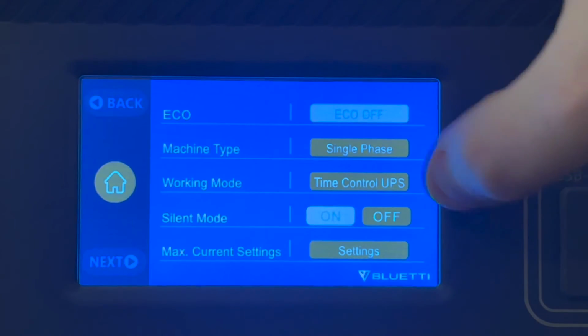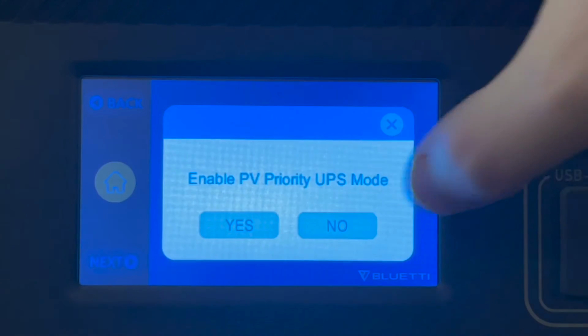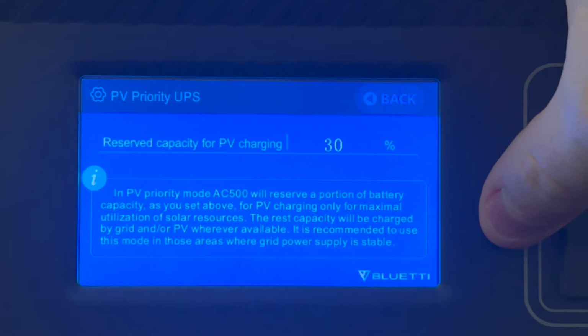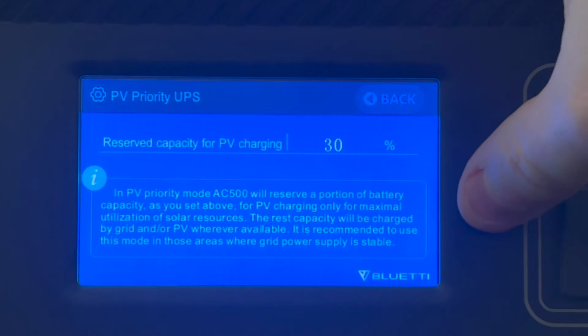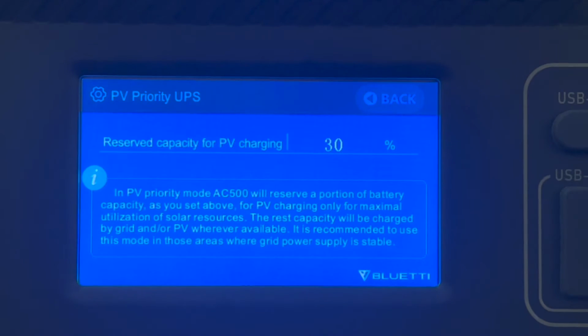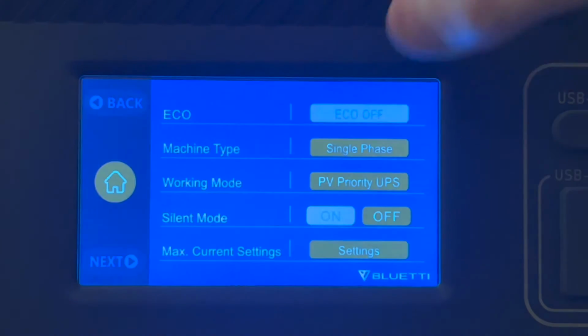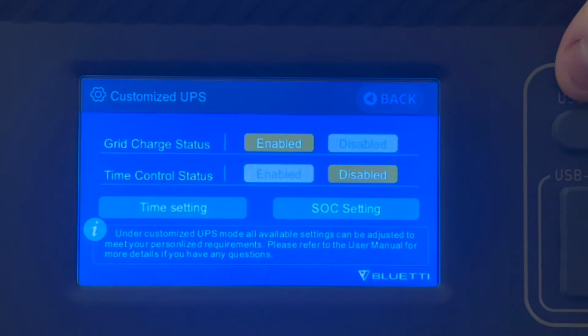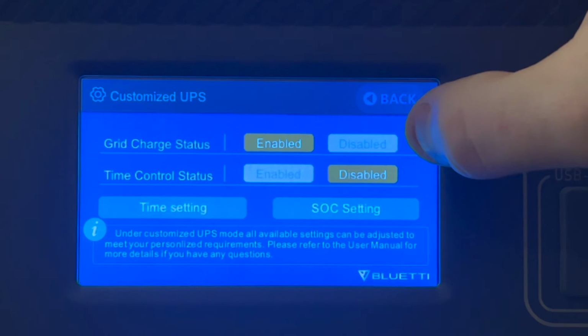Okay, so now I can go to the next mode, PV priority. PV priority is going to reserve a portion of the battery, as you said above, for PV charging only. Exactly the same thing as the high and the low percentage in the previous mode. It's going to charge from AC until, in this case, it gets to 70%. It's going to reserve 30% for PV charging. That's to save on your power bill. Customized is all of them mixed together. The one thing you can do with customized that you cannot do with the other ones is you can turn off grid charging entirely.